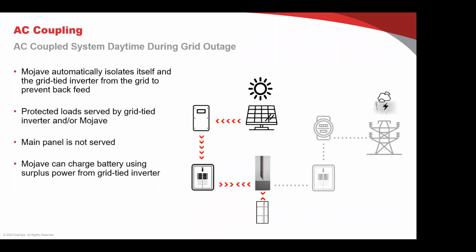Hey, Mark, sorry, I actually have a question here. For the main panel, if we did add an automatic transfer switch to the main, would we still be able to power up the main loads? We would not, because there's no grid signal for us to sync to. If there's no grid power here on the AC input, then by our UL listing we have to maintain that as an open circuit. We can't backfeed the grid.